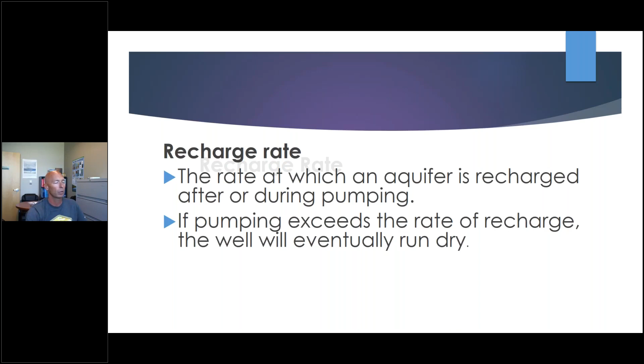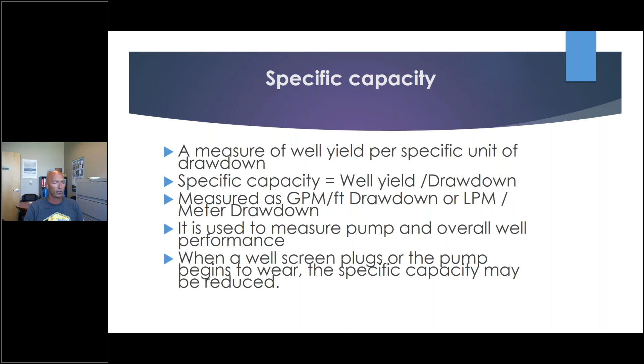Getting to what we do when we do a well test, which is the most important thing at the start of the life of the well, to be able to determine what we're going to put in for a pump. We do this by what's called specific capacity, a measure of well yield per specific unit of drawdown. So specific capacity equals the well yield per drawdown, measured as gallons per minute per foot of drawdown, or liters per minute per meter of drawdown. It is used to measure the pump and overall well performance. When a well screen plugs or the pump begins to wear, the specific capacity may be reduced, and that's for sure.